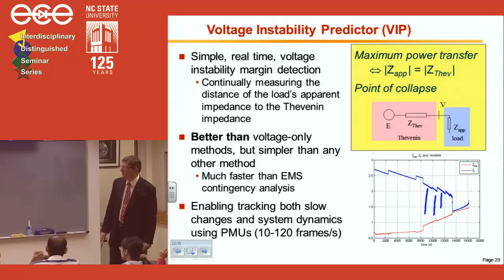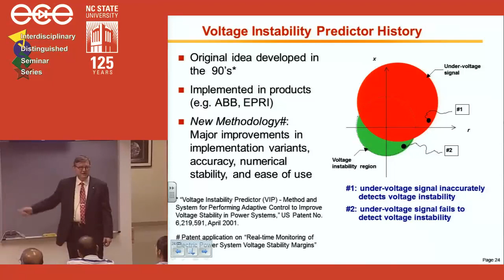Let me show a simple example. If the voltage instability region is green on the RX diagram, here's what an undervoltage signal really does. At point 1, voltage is getting low and you trip, but it's still not unstable. At point 2, voltage isn't too low, but shunt capacitors keep it artificially high. Because you're close to the knee and lack dynamic sources of reactive power, you get a precipitous voltage drop and trip immediately into voltage instability—something your regular undervoltage relay won't tell you.